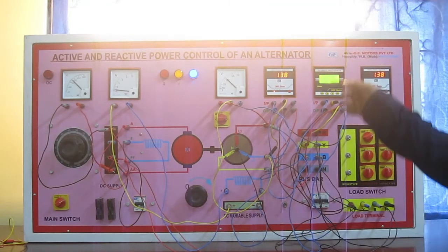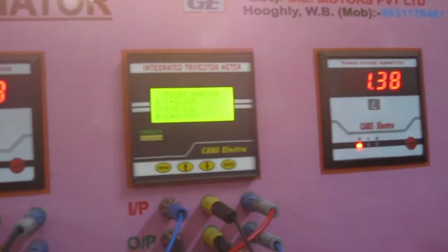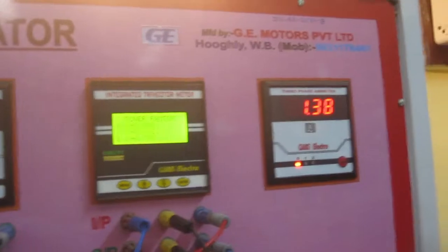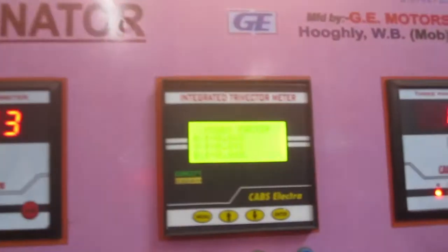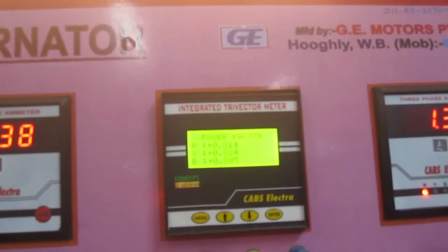Look at the power factor meter — power factor is plus 0.8. Now I will show you: this is pure inductive load, resistive and inductive load. So power factor was minus 0.8. Then I will apply the capacitive load. Look, this is C1 applied, so power factor is plus, that means it is leading.